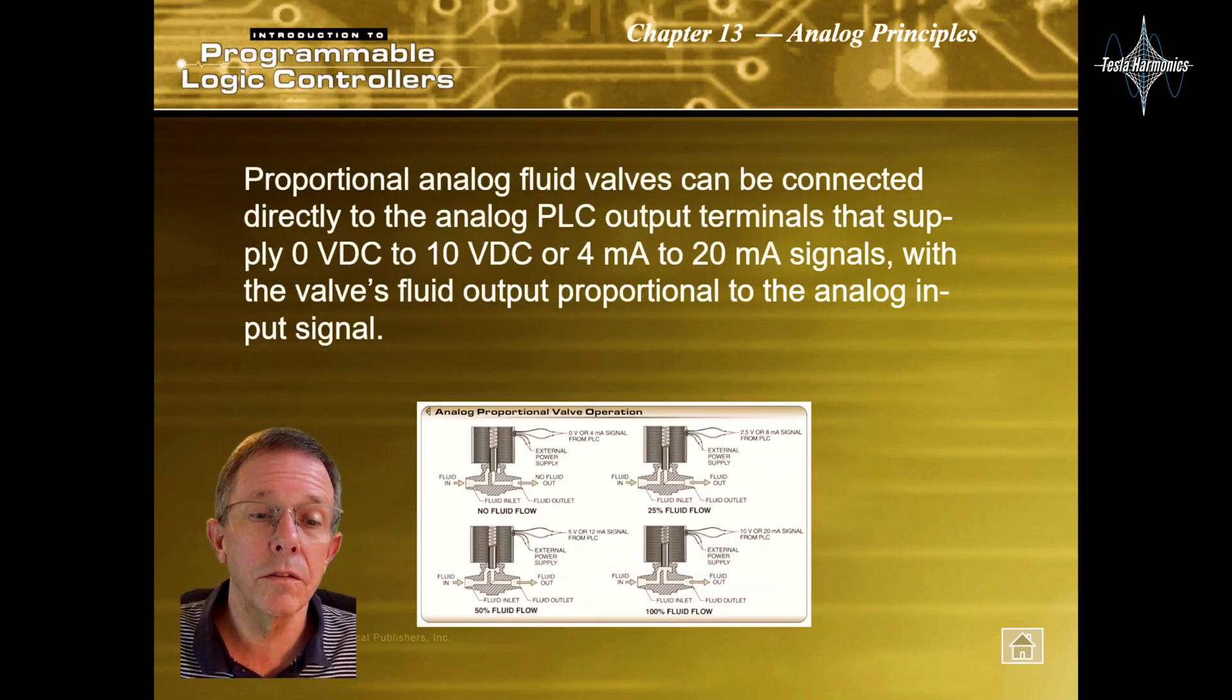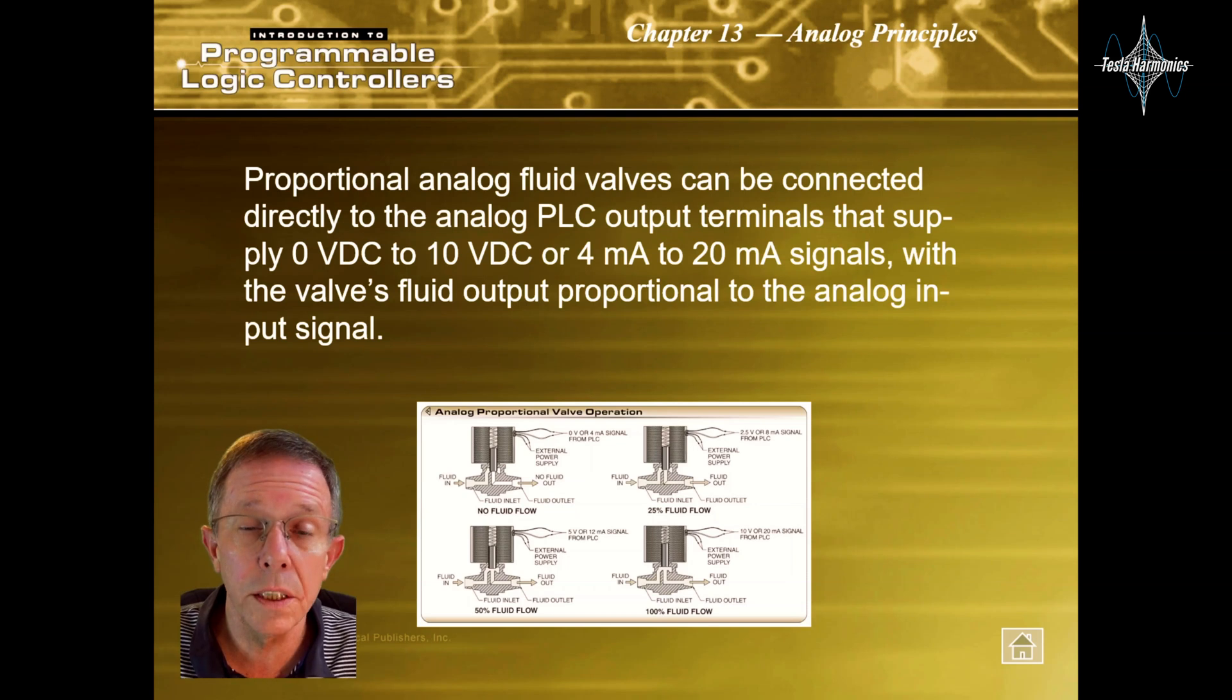Proportional analog fluid valves can be connected directly to an analog PLC output terminal that supply 0V to 10V DC or 4mA to 20mA signals, with the fluid valve output proportional to the analog's input signal.